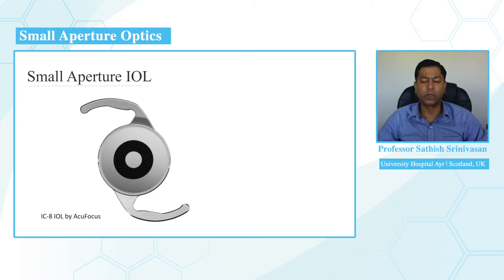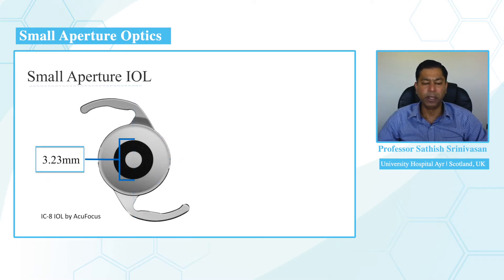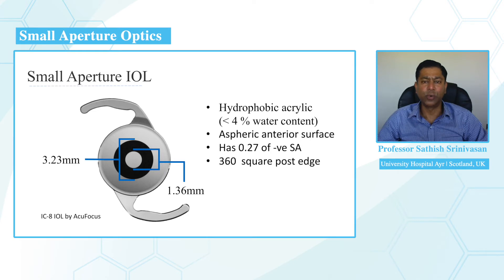The IC8 is a small aperture intraocular lens manufactured by AcuFocus, based in California. It is similar to a standard monofocal IOL — a single-piece hydrophobic acrylic lens with modified C-loop haptics. It has a 6 millimeter optic and an overall diameter of 12.5 millimeters. At its center is a mask measuring 3.23 millimeters with a central aperture of 1.36 millimeters simulating an artificial pupil. It features an aspheric anterior surface, 360-degree square edge to reduce posterior capsule opacification, and 0.27 microns of induced negative spherical aberration to counteract positive spherical aberration from the human cornea.